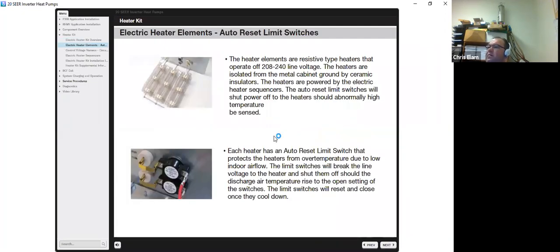The auxiliary electric heaters, the elements are resistive type heaters that operate off of 208 to 240 line voltage. The heaters are isolated from metal cabinet ground by ceramic insulators. The heaters are powered by the electric heater sequencers. The auto reset limit switches will shut off power to the heaters if the heat becomes abnormally high. Each heater has an auto reset limit that protects the heaters from over temperature due to low indoor airflow.